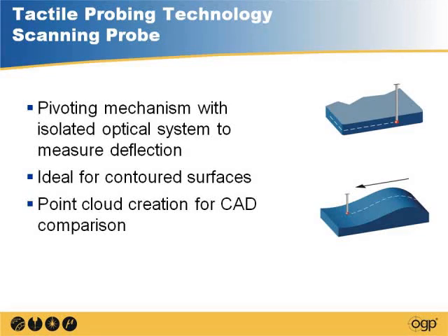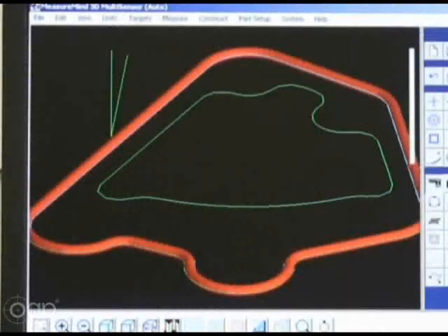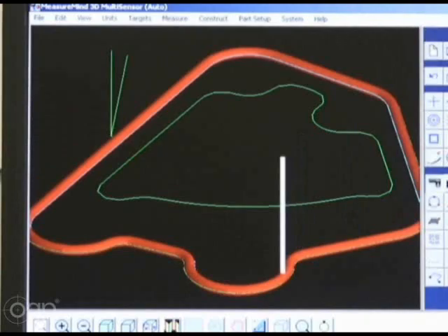What happens is it scans at a constant force, and as it detects the deflection, it will actually change the servo direction to keep the probe at a constant deflection away from the part. So let's take a look at that. This is a video of a scanning probe scanning around the exterior of this black part. You can see how it maintains a constant deflection. This is a little model window of the simulation of it, and that's how it's used to help program it.